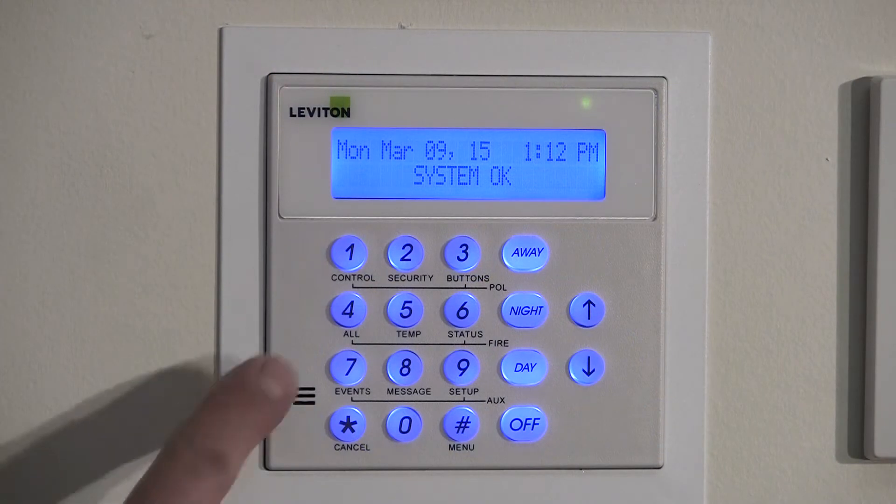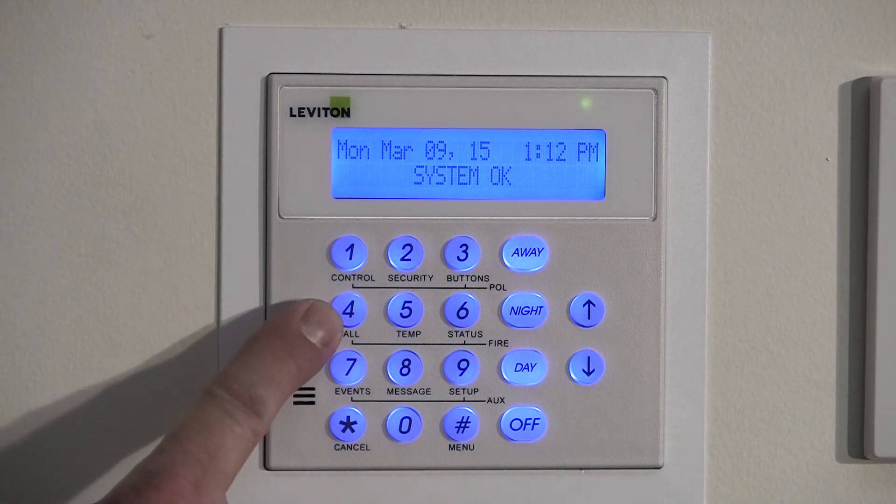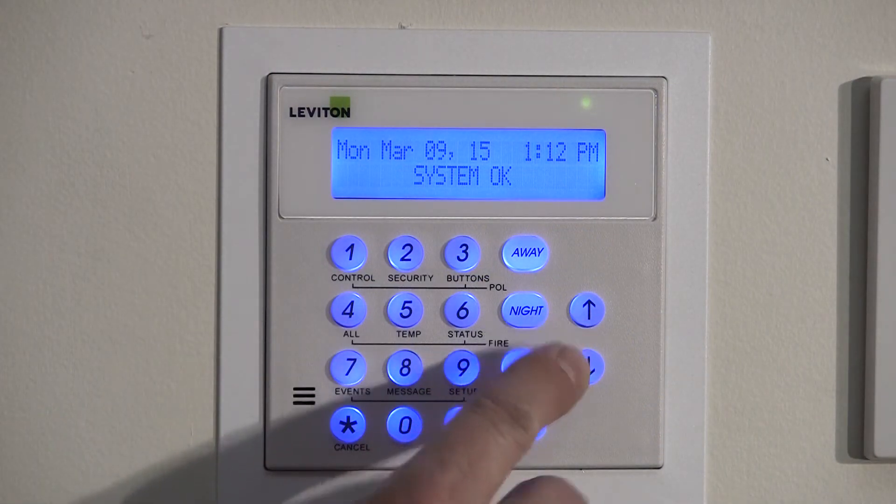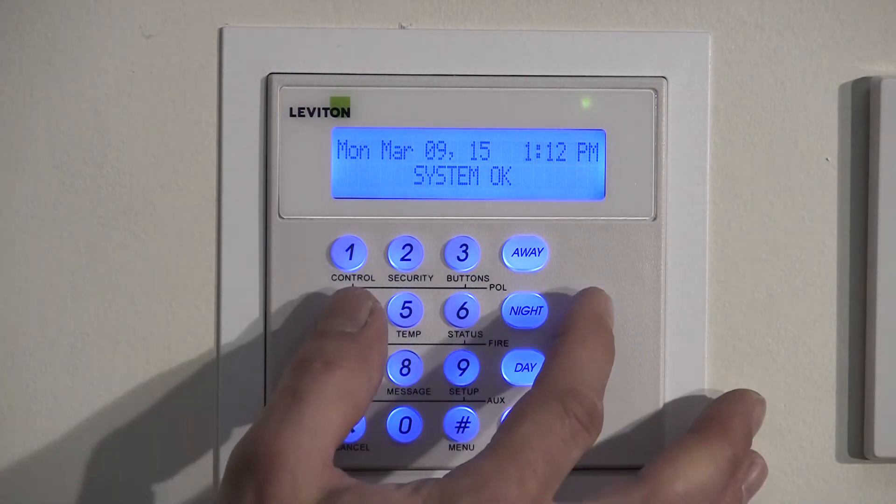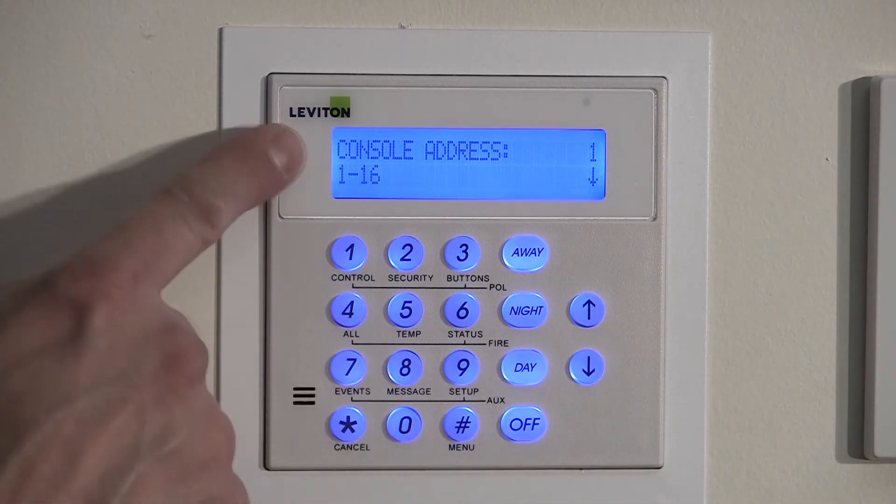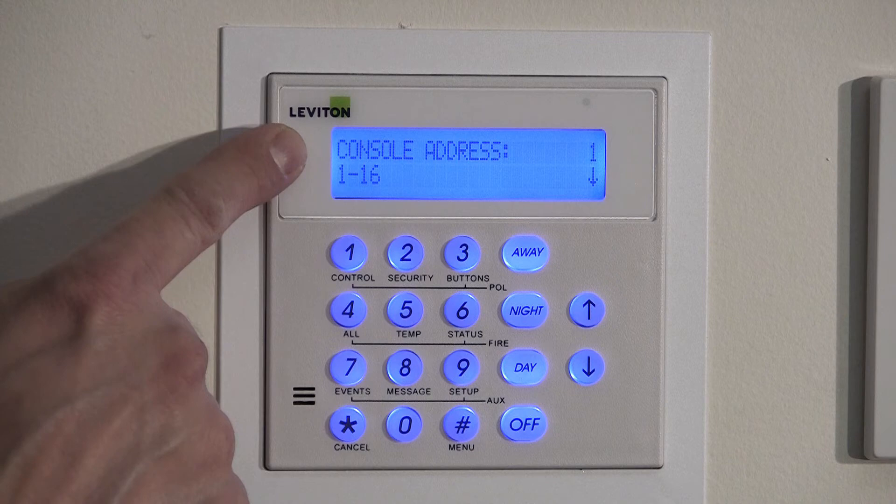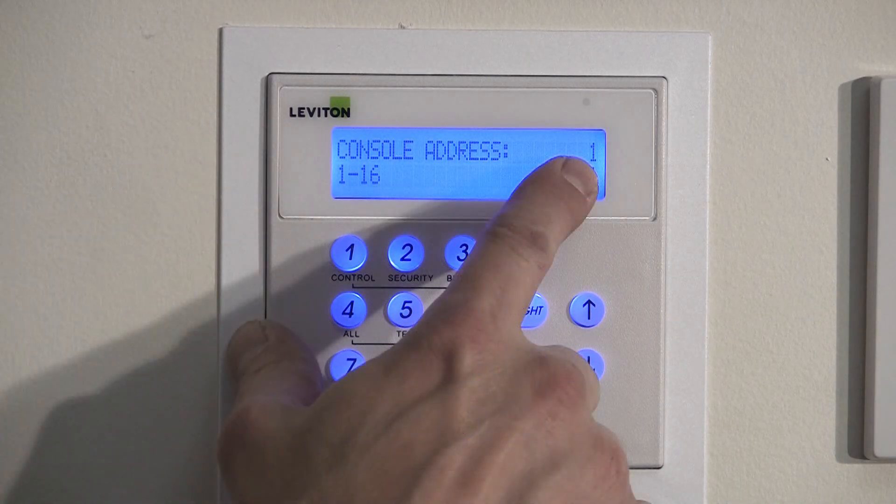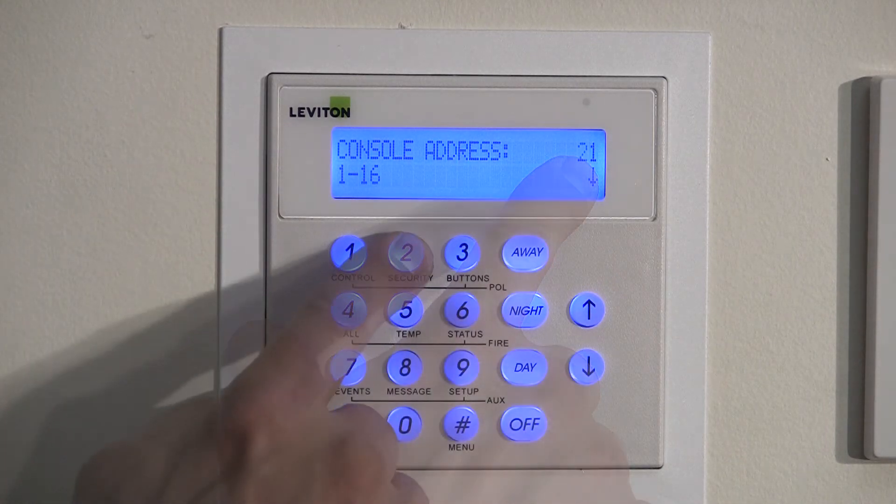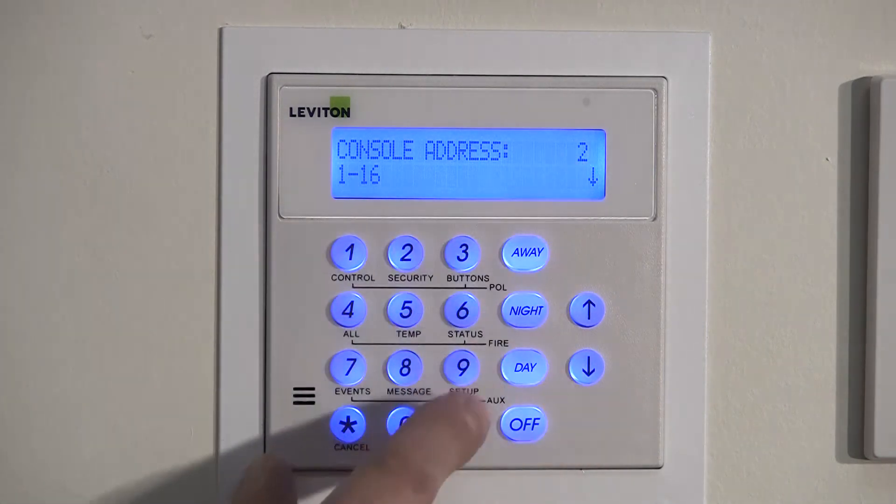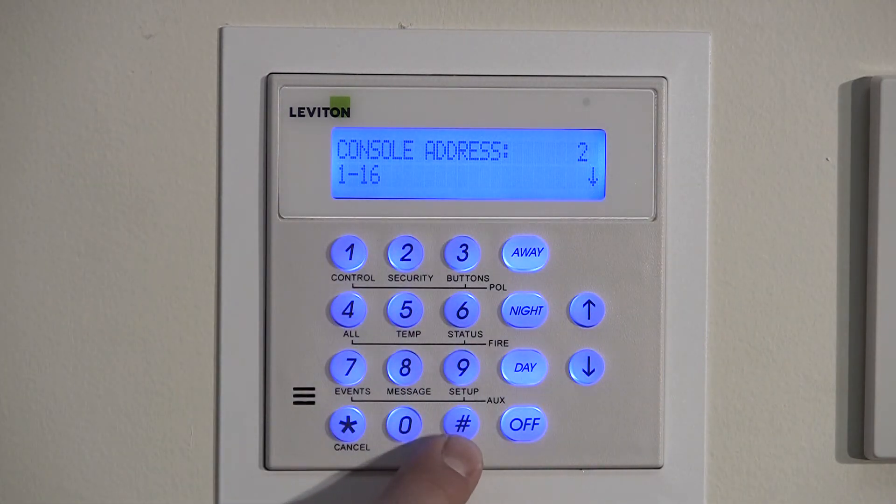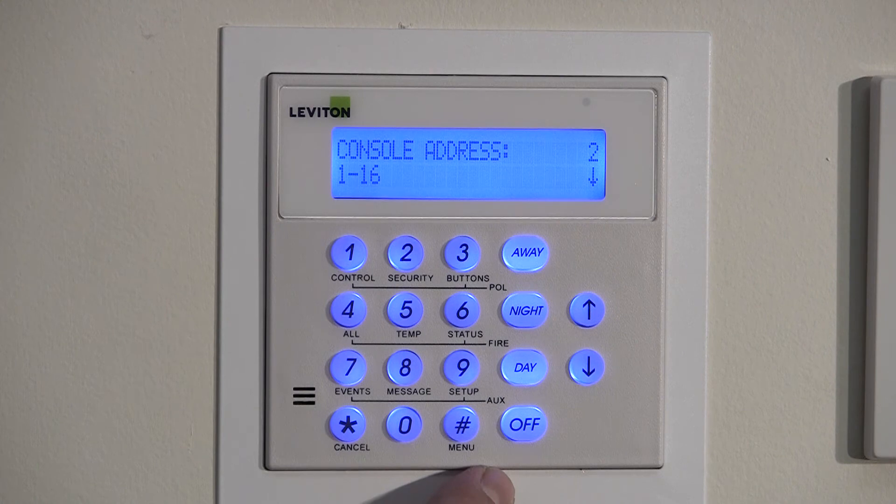Simultaneously press and hold the 4 and up arrow for approximately 2 seconds. You will hear 5 beeps and the console will enter the internal setup menu. The display will show console address on the left hand and the current address on the right. Enter in the desired number and press the pound key to save. Note, on Omni LTE, only addresses 1 through 4 can be used.